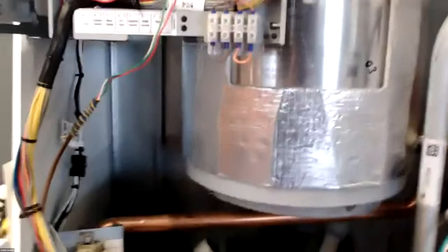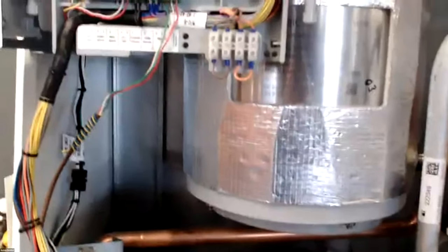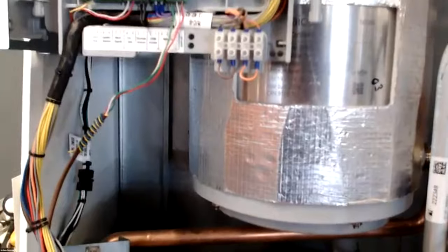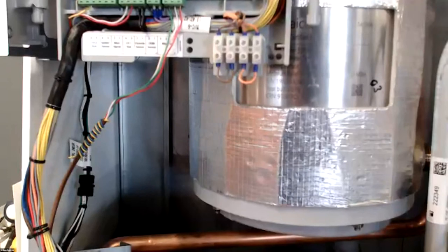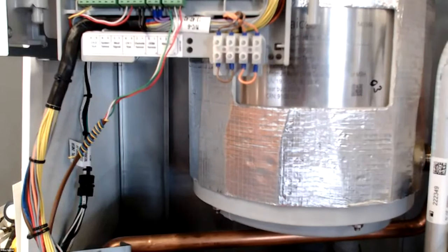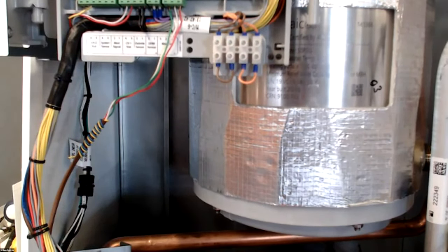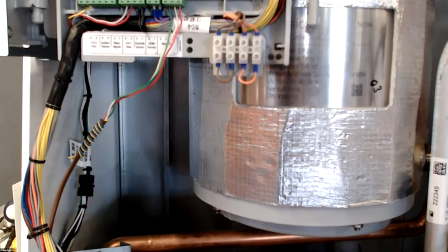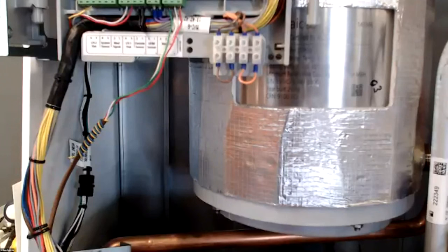And that is the line voltage connections. Wiring the boiler, make sure you have the correct polarity. Hot coming in goes to L, neutral goes to neutral, and your ground goes to ground. Also make sure you have a good ground back to your panel. That's gonna keep your ignition consistent and reduce any issues with flame failures or failed ignitions. So make sure your wiring is good there back to the panel on ground.